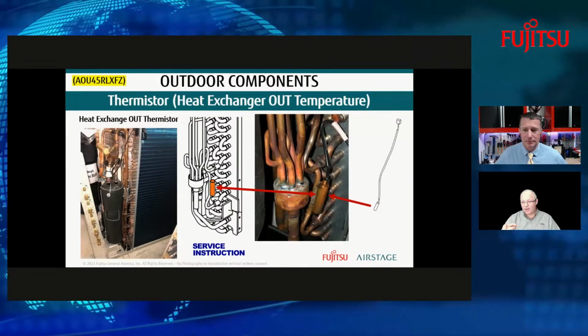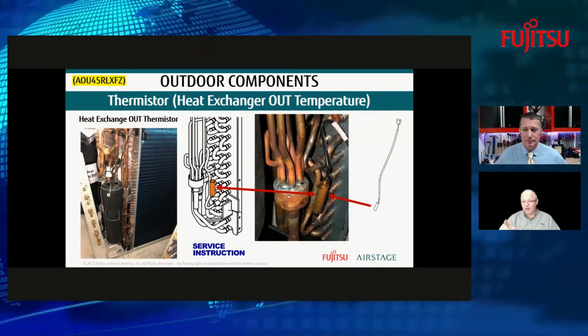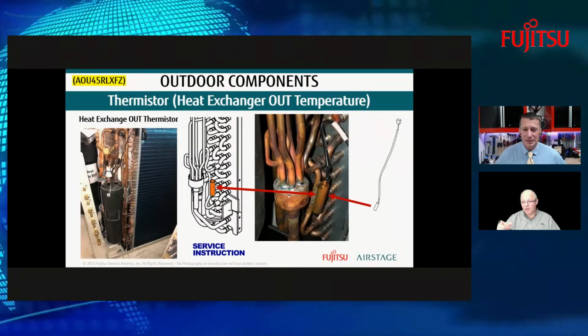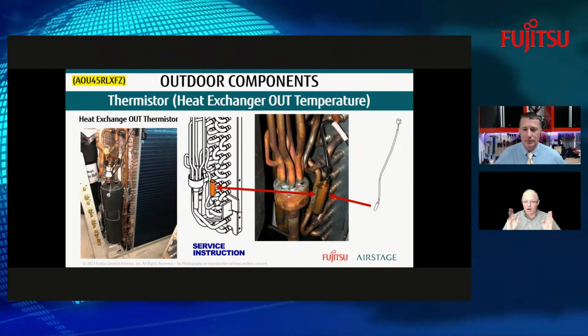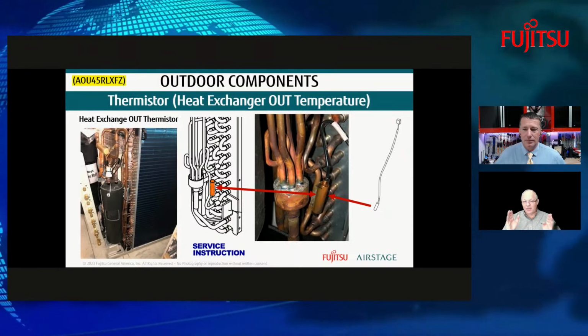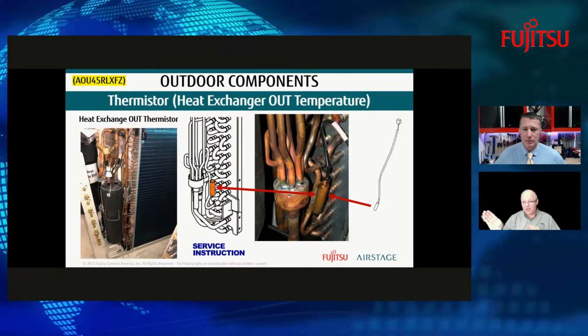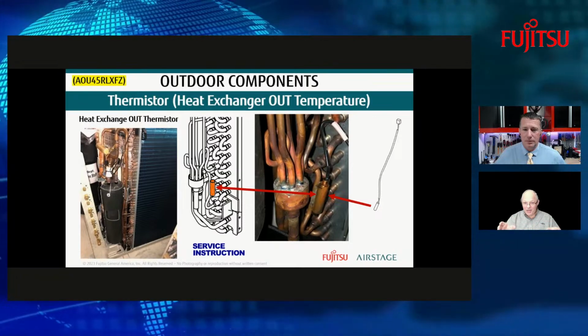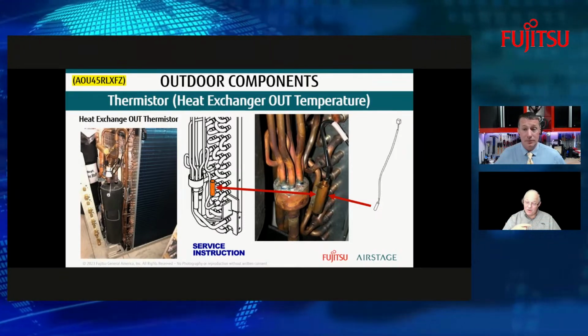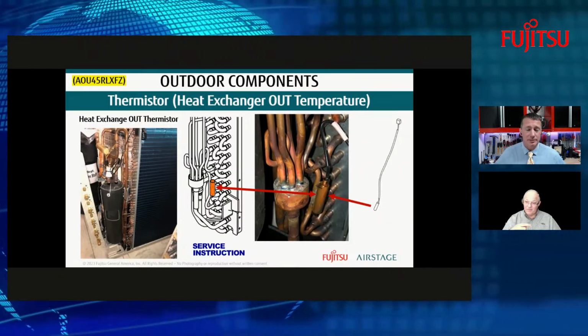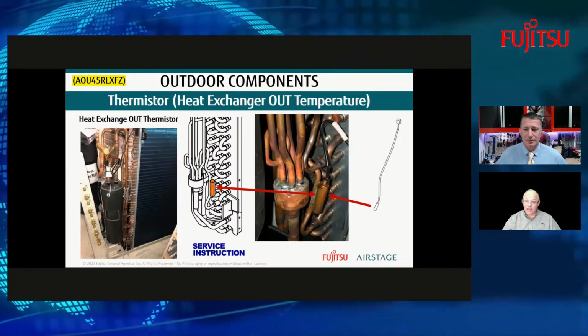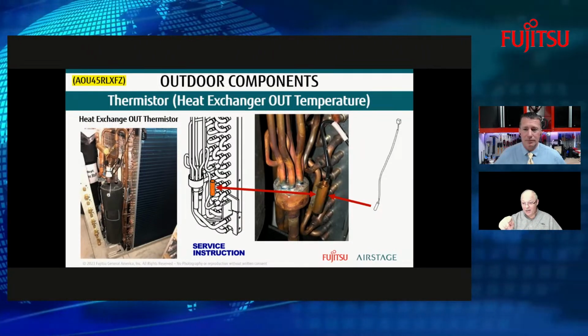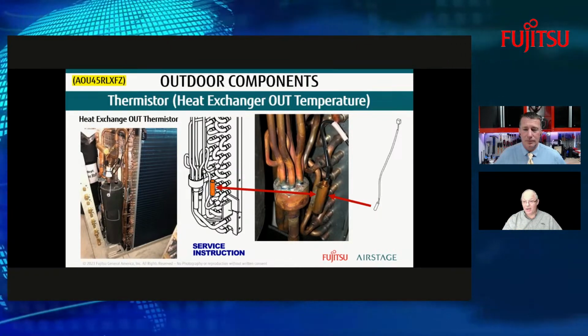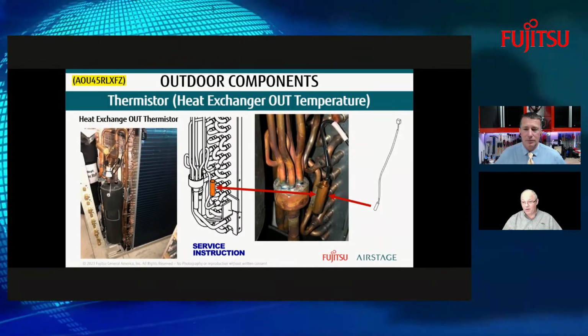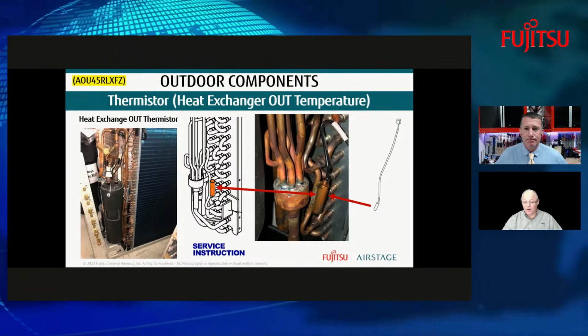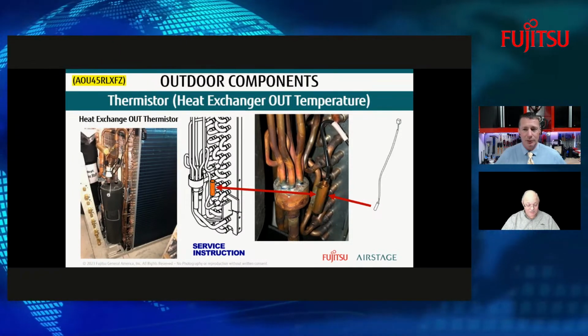The second one here is this one, because this one's going to determine whether or not we're staying within the subcooling range. Exactly. So the system needs to be monitoring subcooling. At the same time, for capacity reasons, we need to know what the outdoor ambient is and what the indoor temperature is. Yeah, absolutely. So that's how we increase capacity. But then controlling subcooling is dependent upon whether we have a clean coil and we have enough air moving across the system to stay within there. Okay.